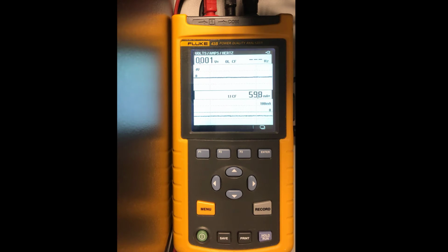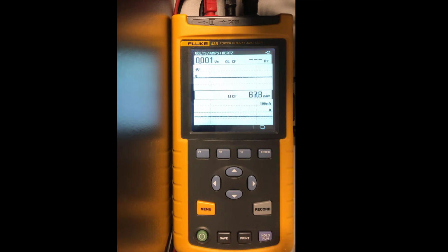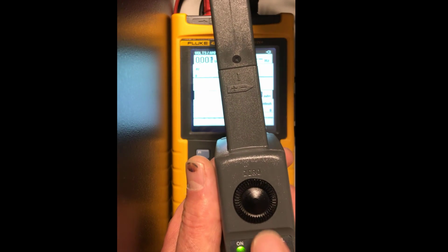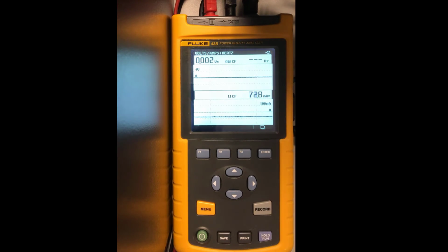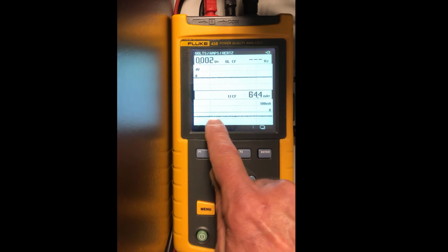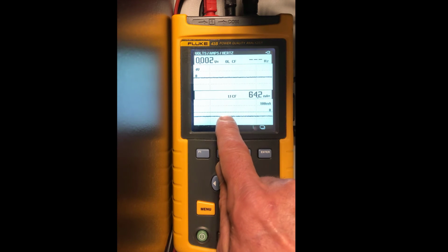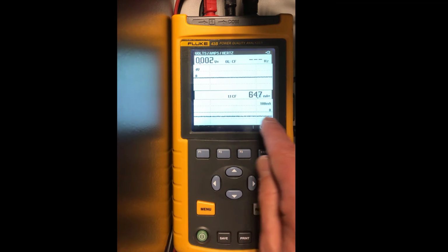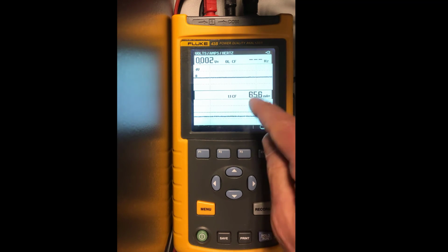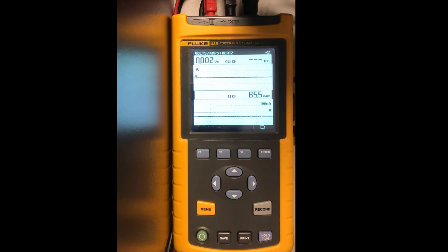Okay, now if you look at that current measurement right now, we don't have the probe connected to any active circuit. And so what we have to do is use this zero steering wheel, I call it, on the top to zero that value to what we're aiming for as a value of current that is below 5 milliamps. And you can see right now it's showing 65 milliamps. Now, one thing that's going to help you is this line you see here, because this line will either be below or above this zero line. You can see it's marked 0 there. It'll either be below or above, but the value won't change from positive to negative.